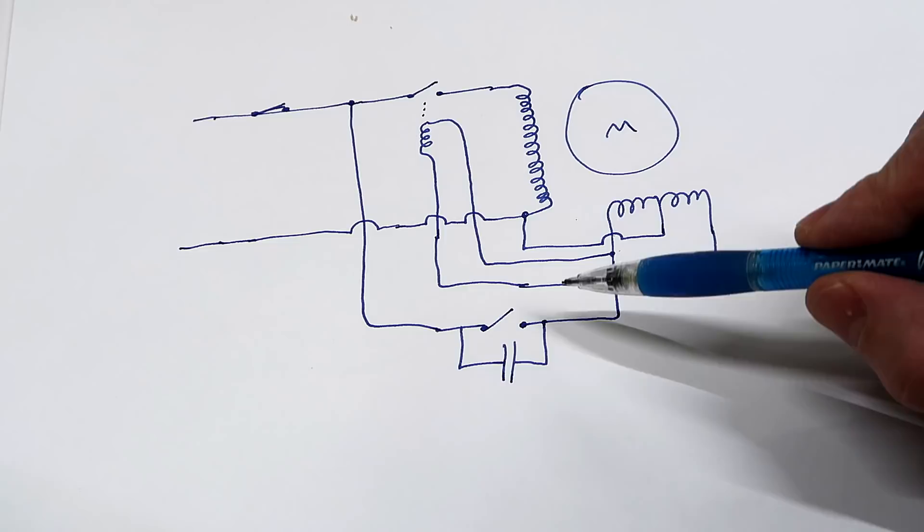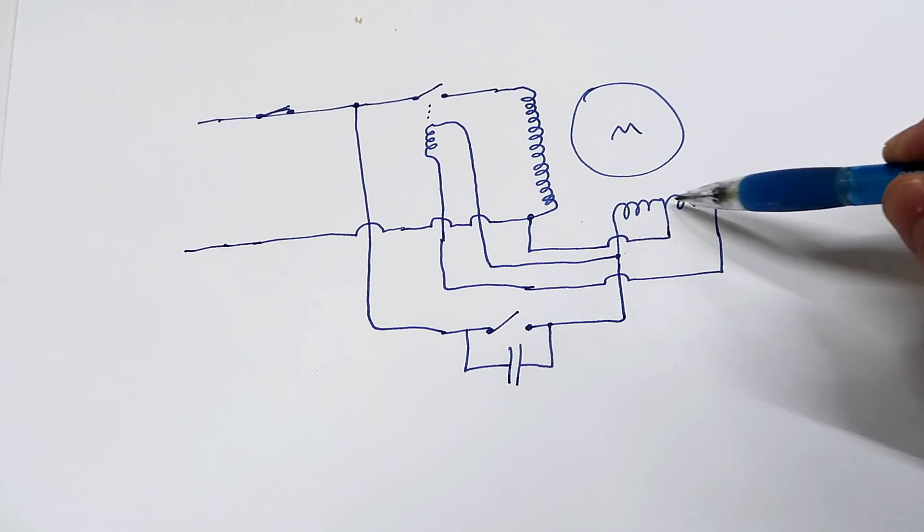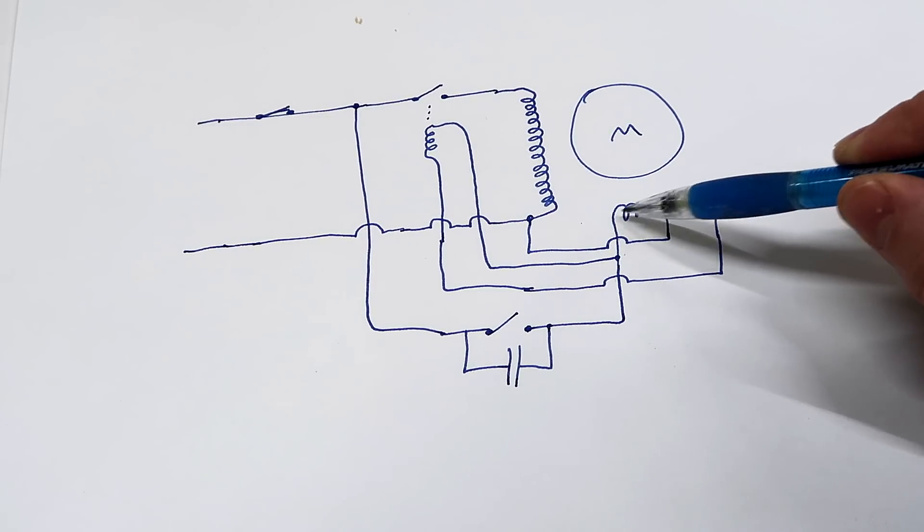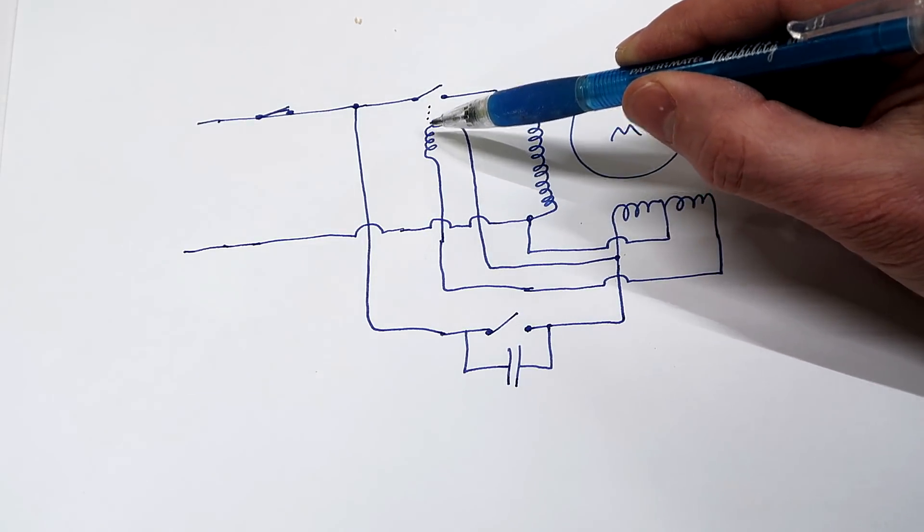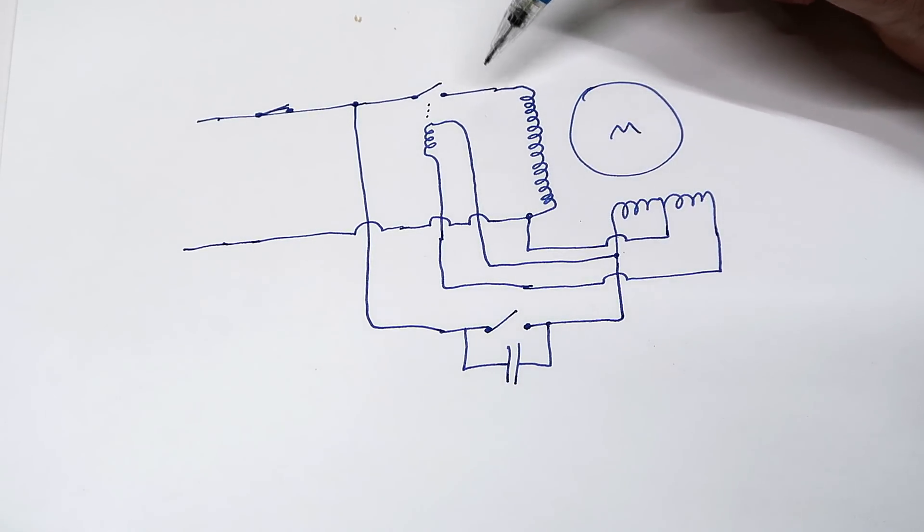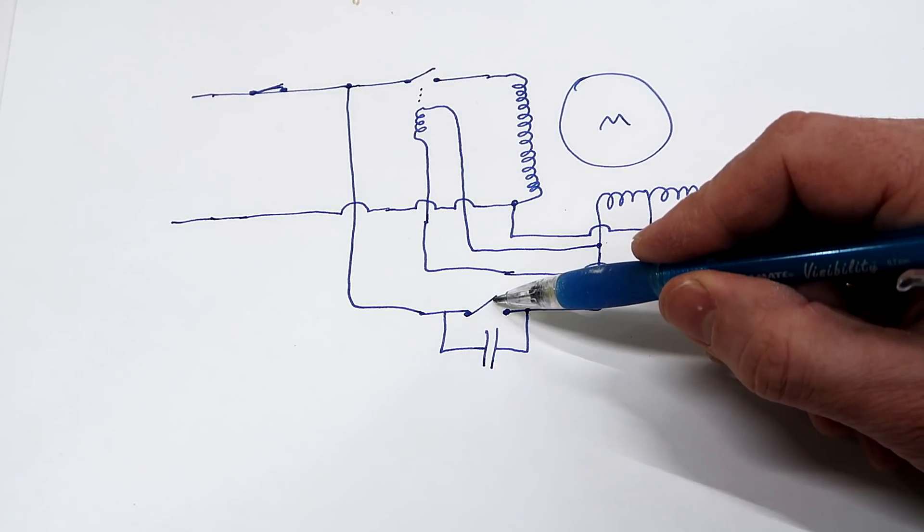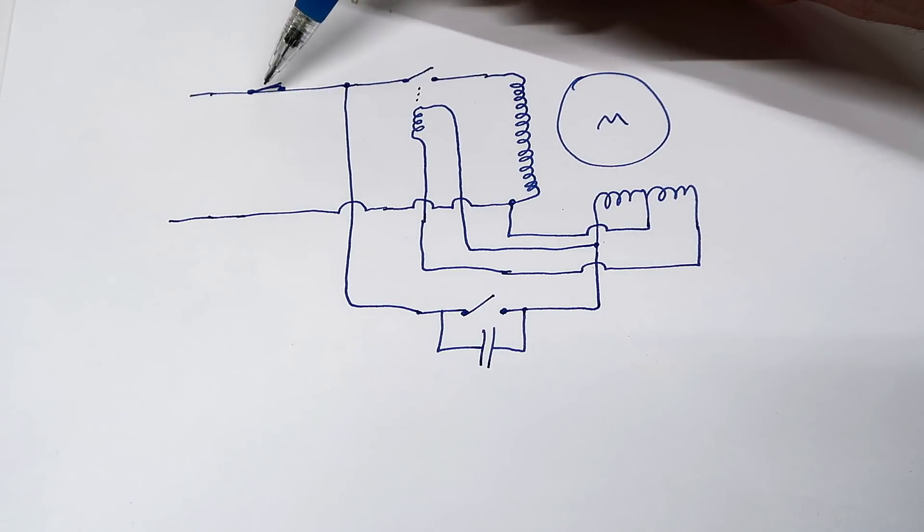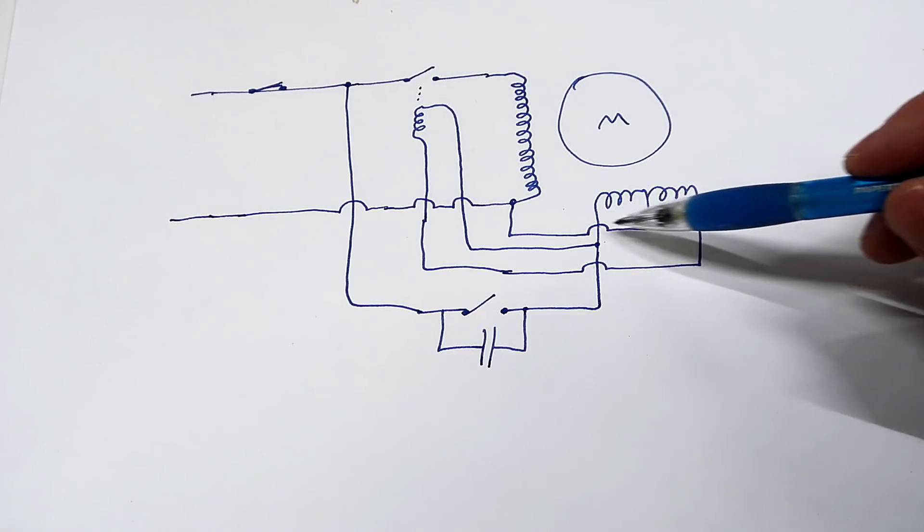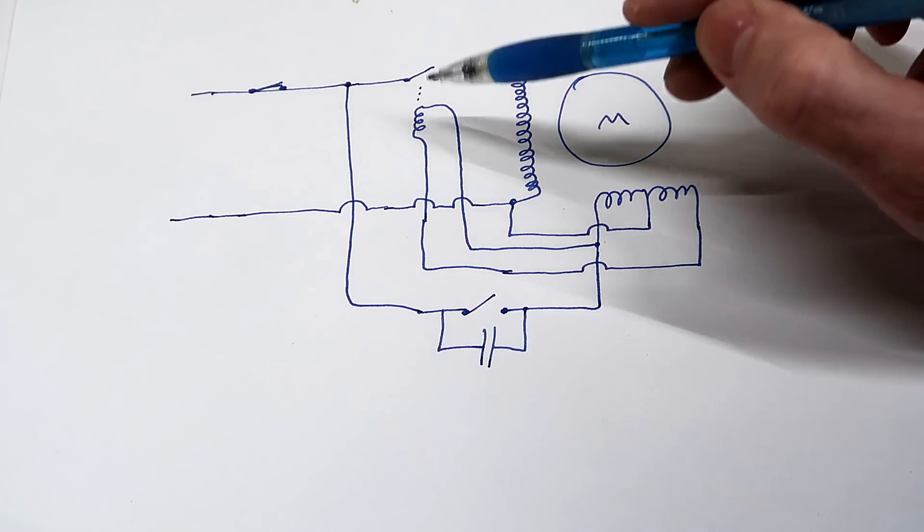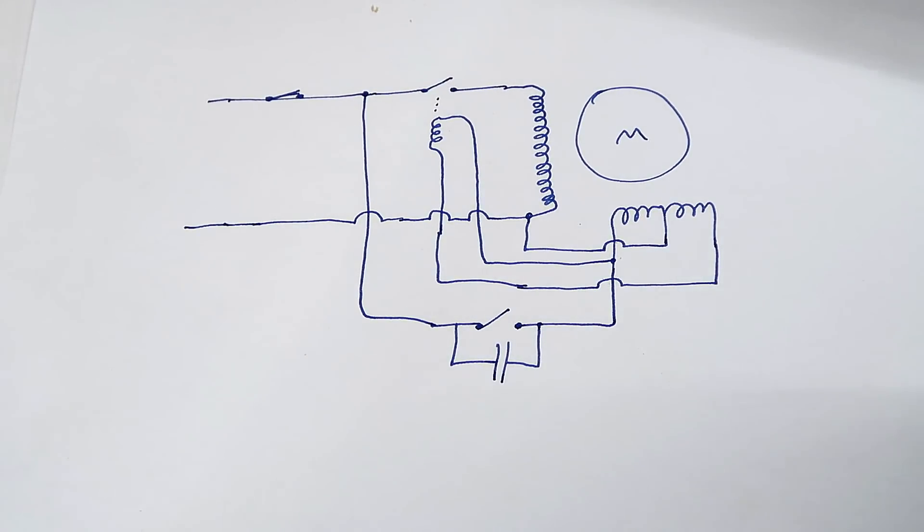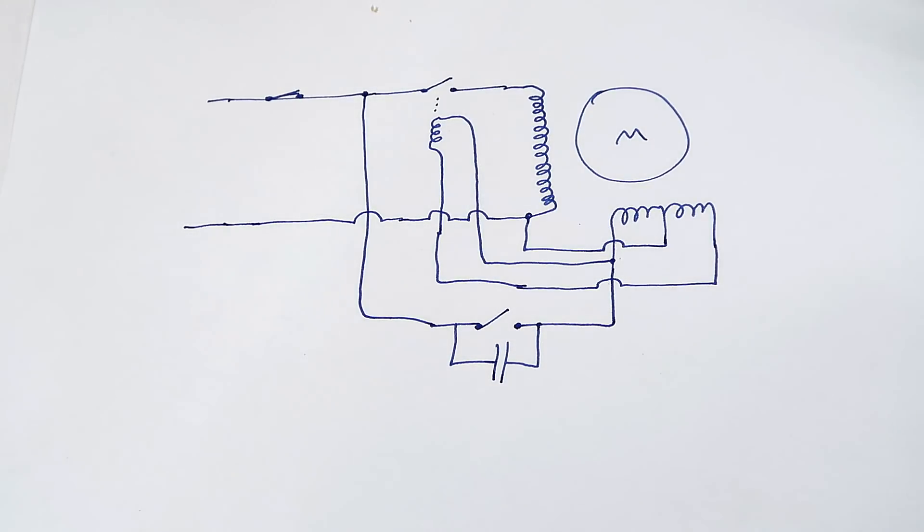So in this circuit, I start by turning on the starter winding. And once the starter winding is engaged, from here to here is more than 100 volts, which engages this coil here of the relay which turns on the main winding. And then when I let go of the start button, that opens up again, and the relay keeps the main winding engaged until I disconnect power with another switch here. At which point without any power to the motor, there's no longer any voltage induced on the starter windings, and the starter relay disconnects. And that means I just need two temporary switches: this one temporarily on and this one temporarily off.